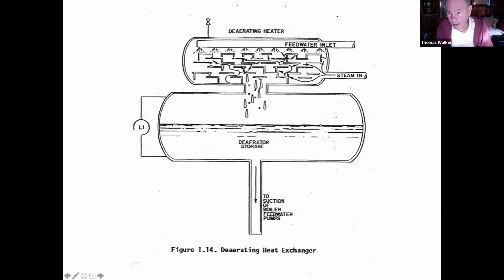Because the steam and water come in direct contact, the water gets heated and it falls into the lower storage section. That gives us a reserve of water that's always located higher than, or above, the feed pumps. So the feed pumps would be down here. The water would flow by gravity into the suction side of the feed pump. That positive suction head makes these centrifugal pumps operate most efficiently.